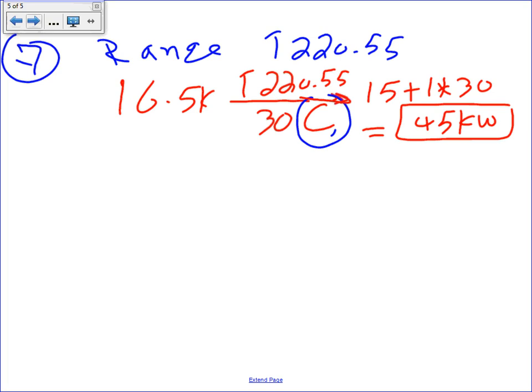We're not done yet. That's step 1, the demand for ranges. All of them are the same size, remember. So we apply note number 1. It will tell you if it's more than 12 kW, for every 1 kW larger than 12, increase it by 5%. What I'm saying right now is note number 1 under Table 220.55. If you read it, it will tell you anything larger than 12 kW range, increase it by 5%.